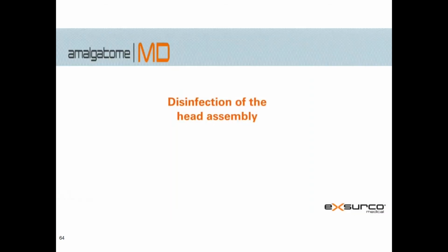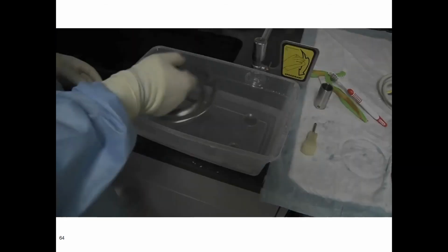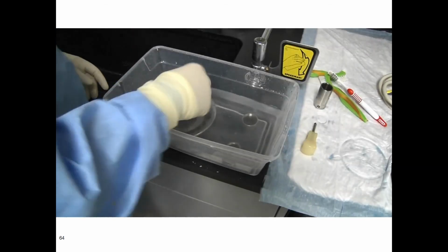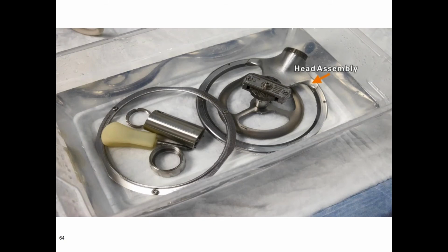Disinfection of the head assembly. Prepare a neutral pH or instrument-safe enzymatic cleaning solution. Immerse the head assembly, blade locking ring, locking knob, locking nut, pin driver, and screwdriver, and let soak according to solution manufacturer specifications.